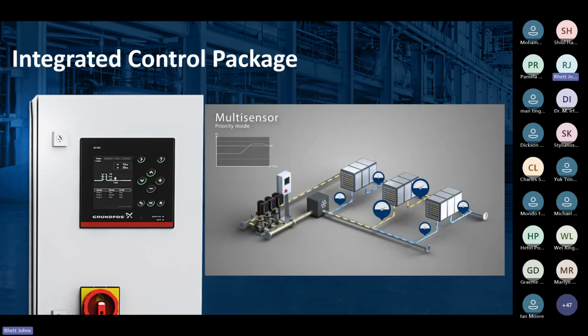And then looking at an integrated control package, what you can do is take the control sensors within your pumps and feed them back to your pump controller, and have them dotted out along the length of your pump system. You can monitor multiple different zones within your pump system and react to drops in pressure depending on the consumption per individual zone.